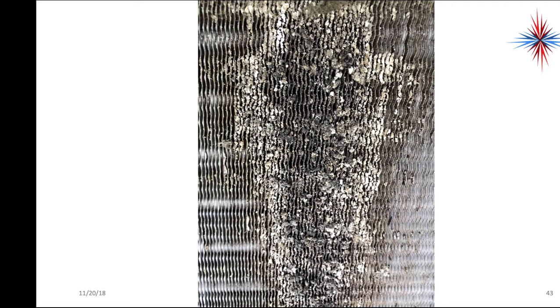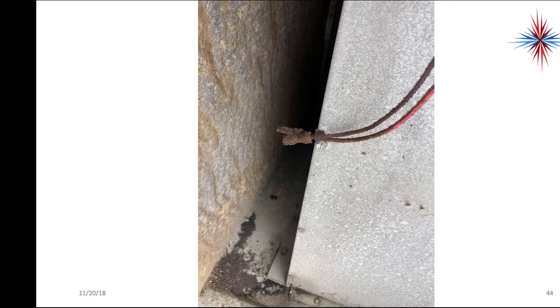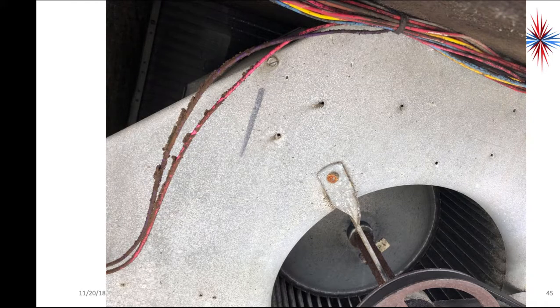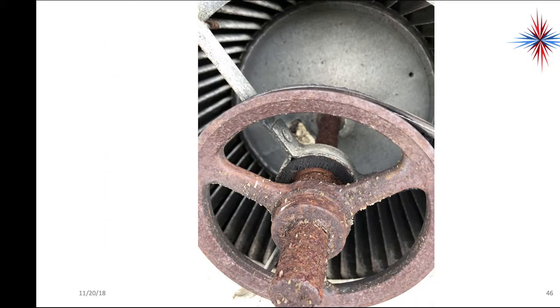Okay, went around and opened up the blower compartment. One of the first things I noticed in the blower compartment was disconnected high limit switches. It's usually not a good idea to ever disconnect a limit switch from a circuit that has electric heat. So I followed it back, found the disconnected circuit, and started taking a look at the blower motor. One of the complaints was that they tried to start this unit up and got smoke in the ductwork, and shut it right down.